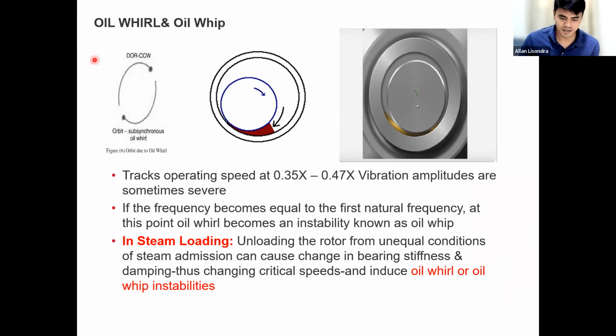If you're working in a power plant, there's what we call steam loading in operation. Loading the rotor unevenly during steam admission can cause changes in bearing stiffness and damping, which changes the critical speeds and can induce oil whirl or oil whip instabilities. That's why it's very important at the beginning that steam loading is done properly, following procedure and requirements, because sometimes you'll notice the vibration is different from the last startup.